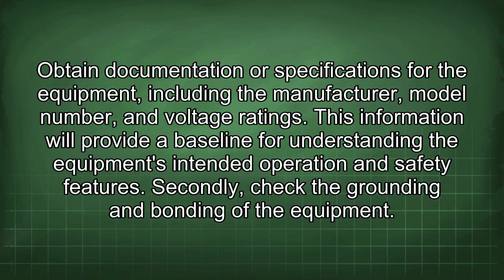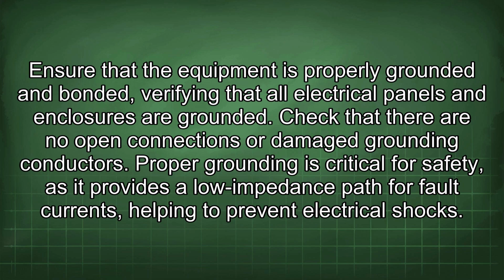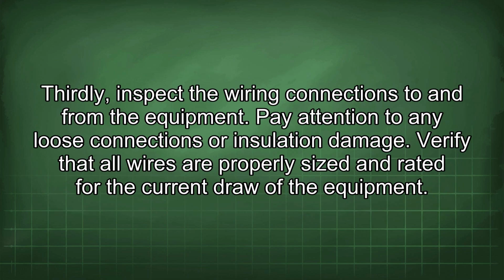Secondly, check the grounding and bonding of the equipment. Ensure that the equipment is properly grounded and bonded, verifying that all electrical panels and enclosures are grounded. Check that there are no open connections or damaged grounding conductors. Proper grounding is critical for safety as it provides a low impedance path for fault currents, helping to prevent electrical shocks. Thirdly, inspect the wiring connections to and from the equipment.